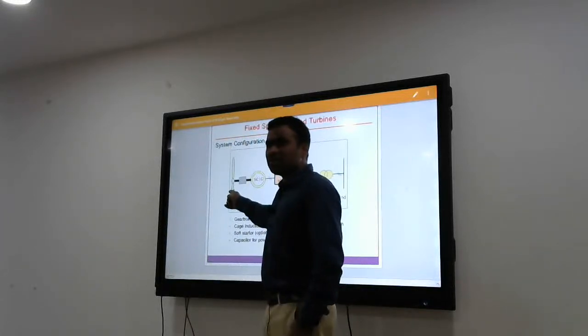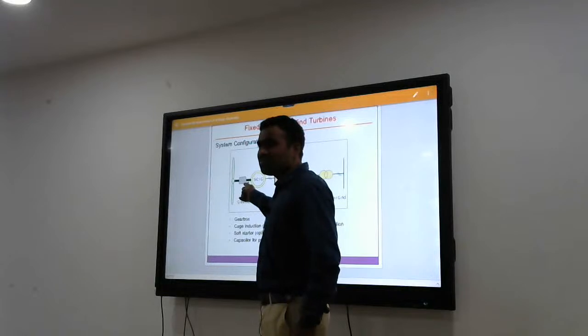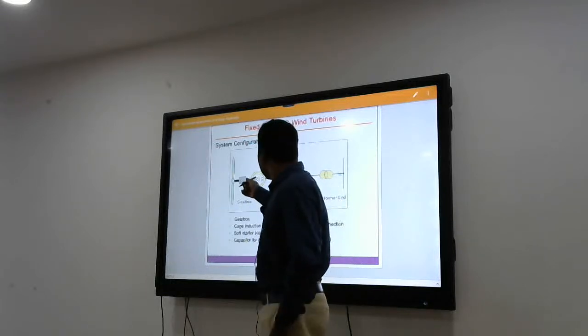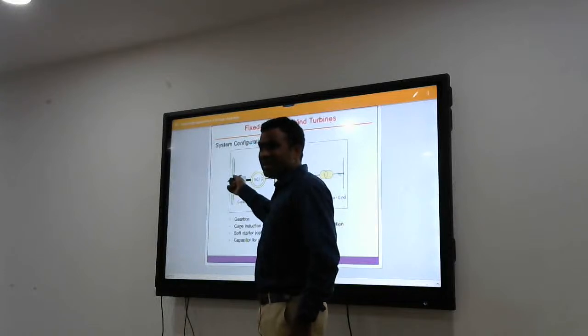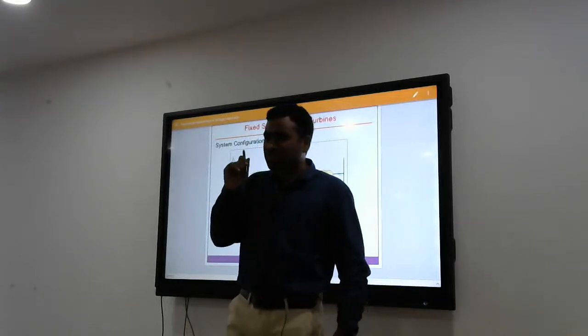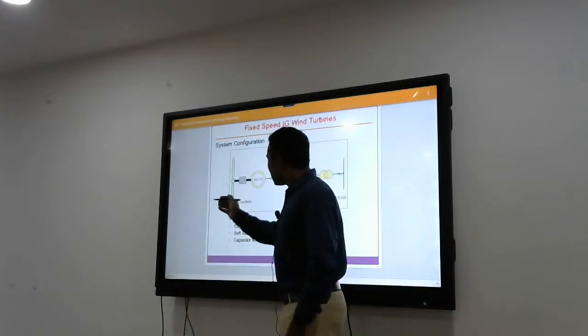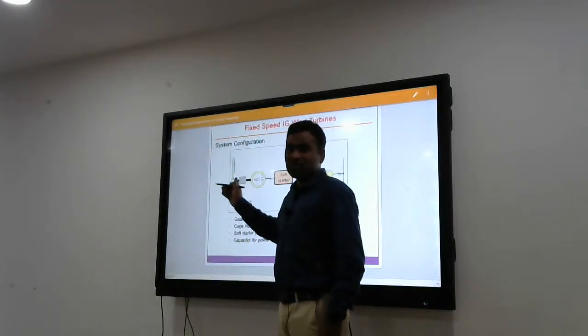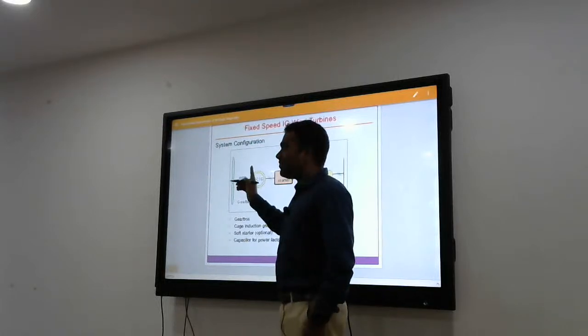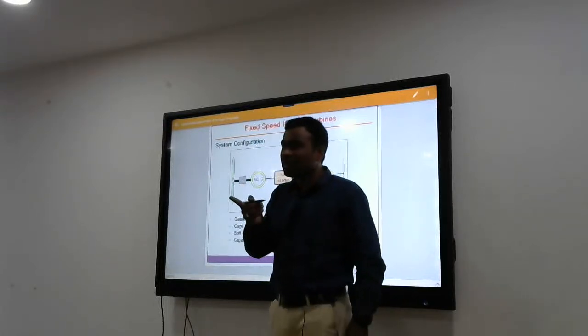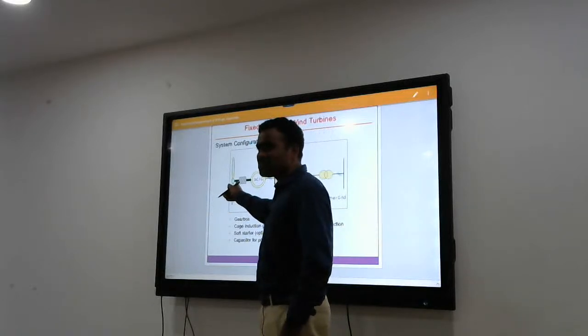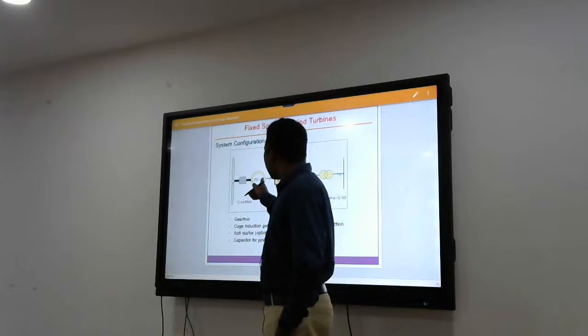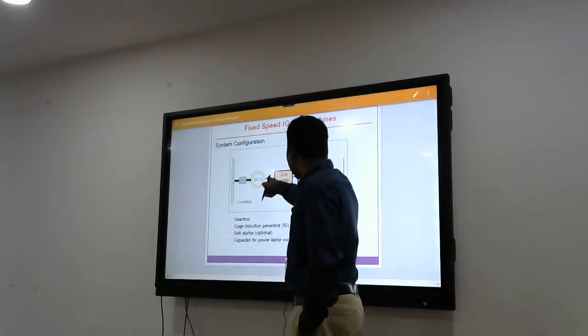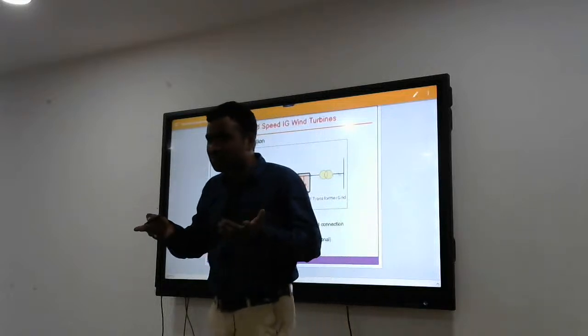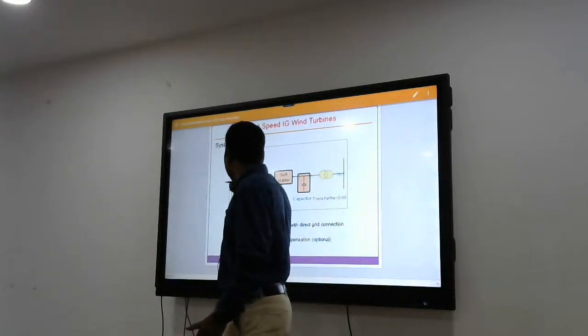Now what you have to do is run this wind turbine at a speed so that your rotor speed is greater than your synchronous speed. You should make sure your speed is greater than synchronous speed, so that this induction machine will enter into generation mode, and the power is generated. Once the power is generated, that will be fed to the grid. That's very simple.